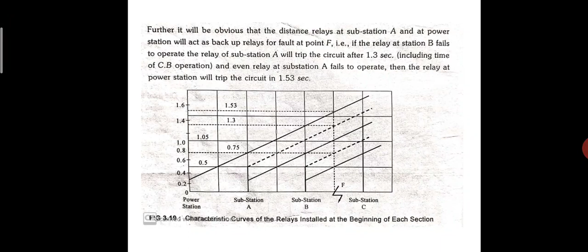For example, if the relay at station B fails to operate, the relay of substation A will trip the circuit after 1.3 seconds, including circuit breaker operation time. And even if the relay at substation A fails to operate, then the relay at power station will trip the circuit in 1.53 seconds.